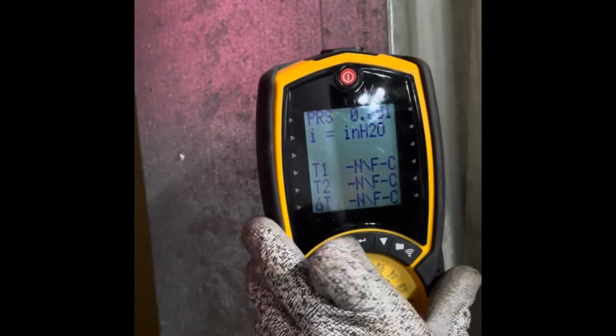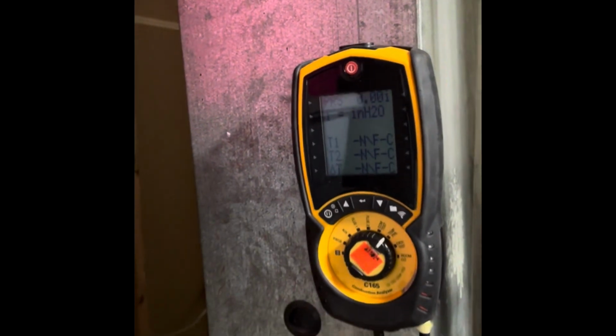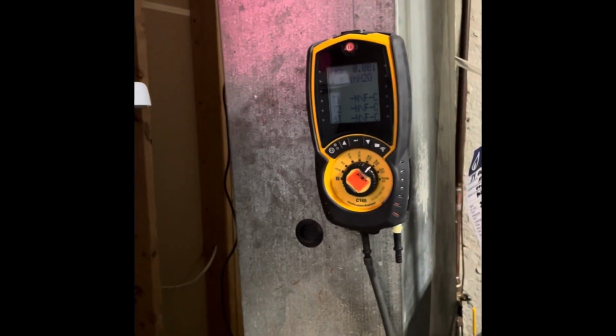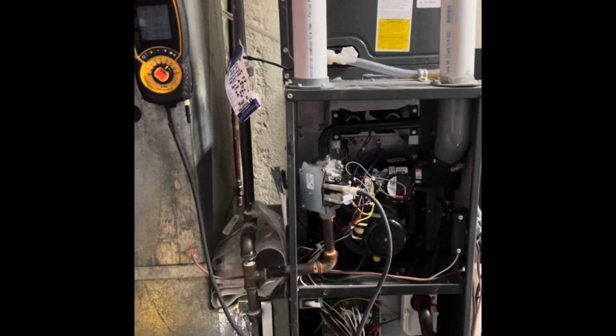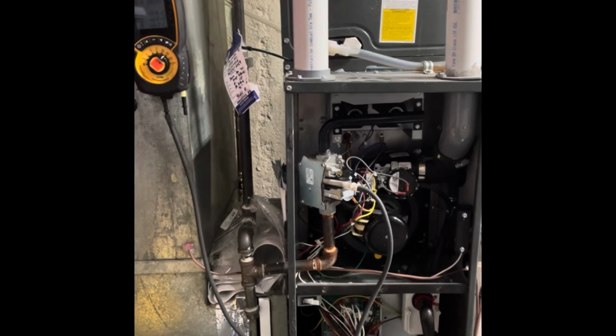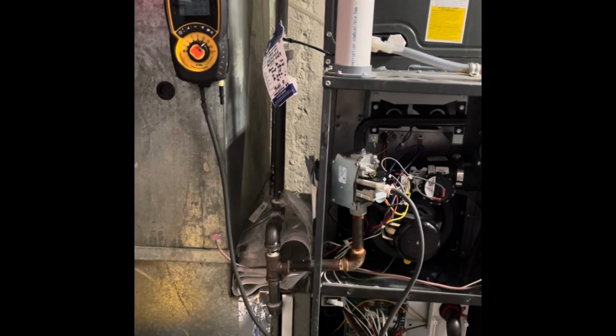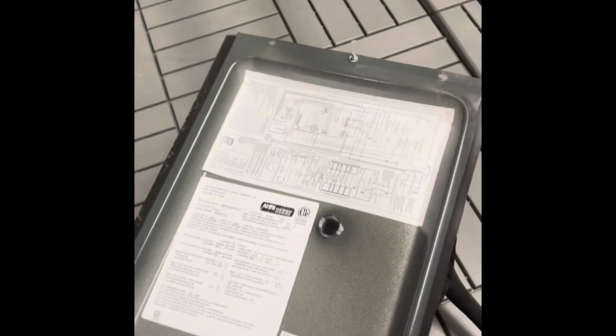I want to check the pressures, as well as I'll be doing a carbon monoxide test in this pipe, making sure that it's under 200 parts per million. Most of our furnaces, we only get a threshold of 100 parts, but this particular Amana unit, we can go all the way to 200 on one. And I'll give a quick explanation what I'm looking for.